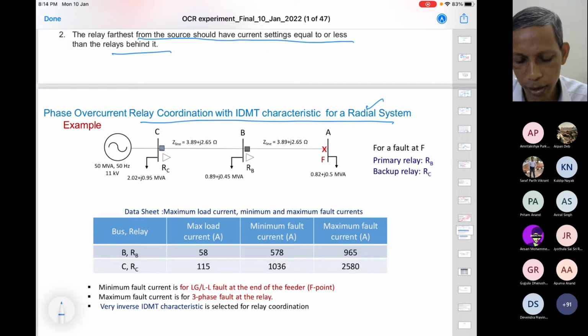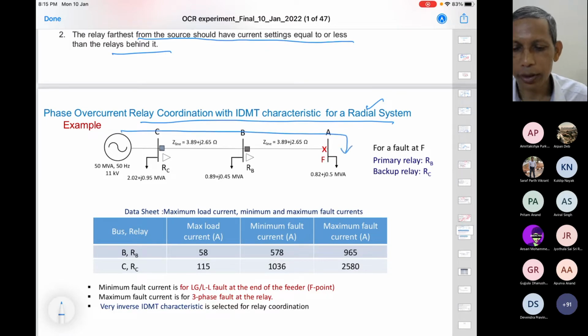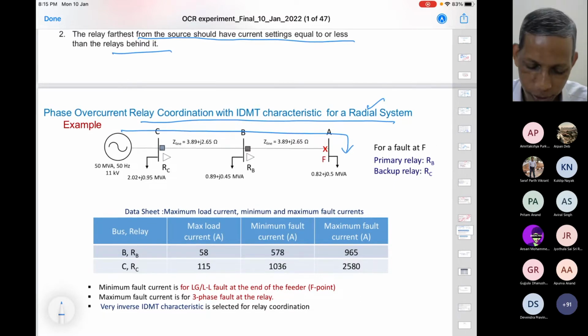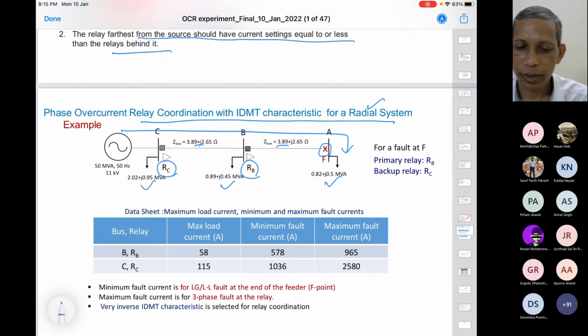Radial means unidirectional power flow. Agree? There is no source to the right. But in today's power system, distribution system, we are putting in rooftop solar and so on, so there is every possibility that current can flow from the right also. Okay, we are not going to that right now. So these are the different loads connected, in terms of MVA. And we have some impedances of this path also, like this. And we have a fault created here. We can create a fault here also. Now our job is to achieve the actual coordination between RB and RC for the given characteristic.